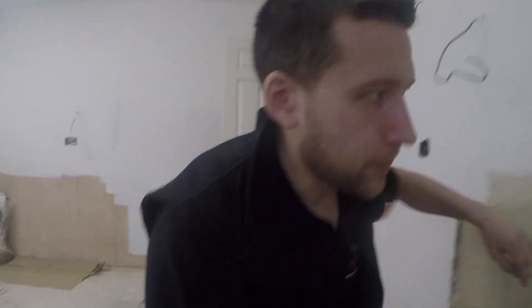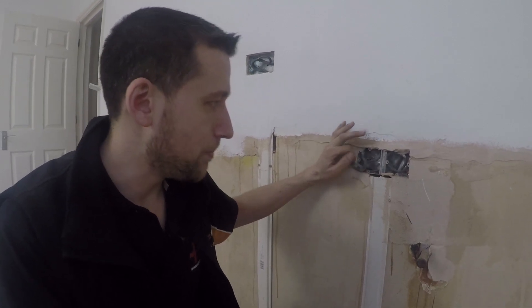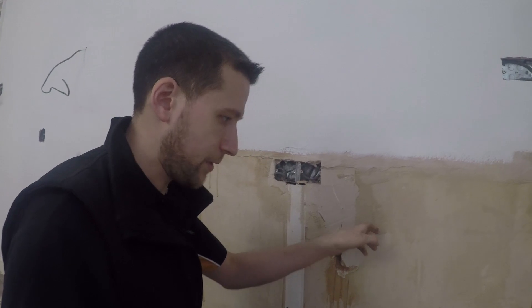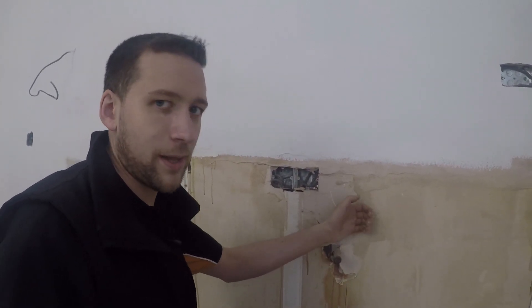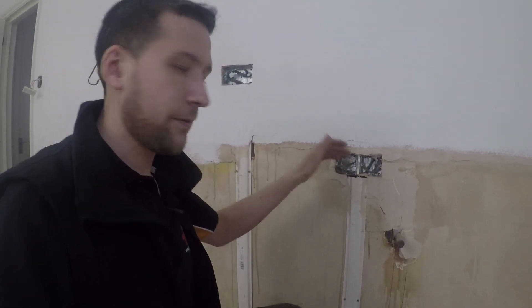Some of you were asking: is this the power supply for the cooker? No it isn't. The one mil for the hob — it isn't actually powering the hob as such, it's just the ignition for the hob. The original six mil cable is actually here — the plaster is plastered over it, the original one is still there, which we'll have to dig out later. So they do still have the original six mil here, but I've just run a one mil off a fuse spur for the ignition.